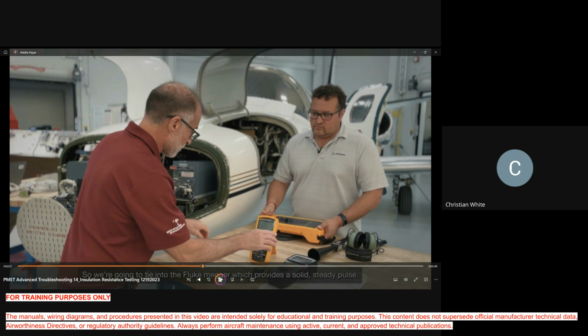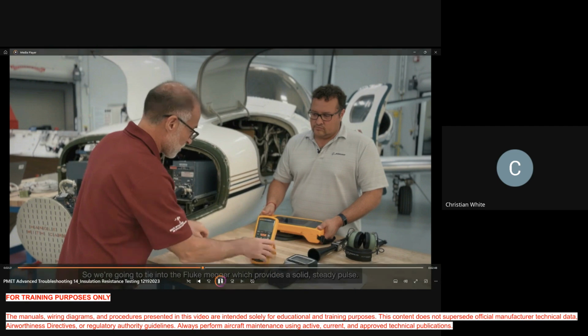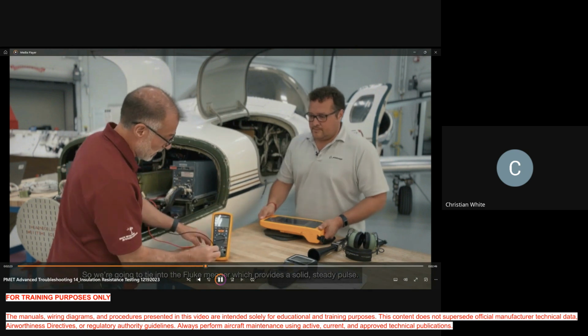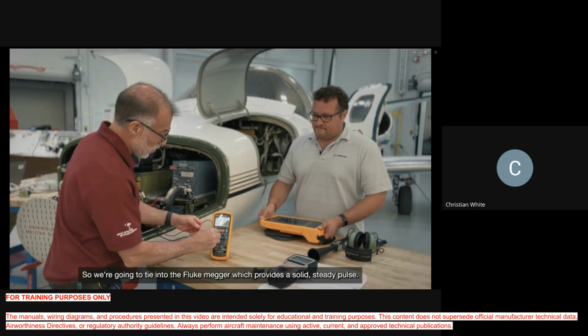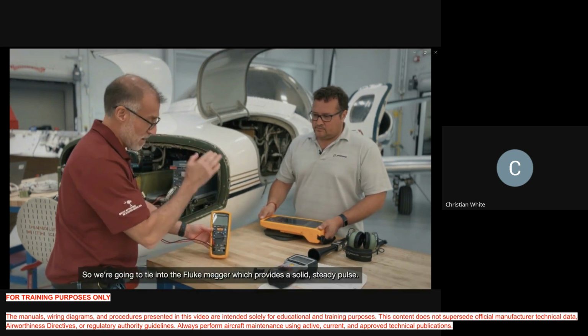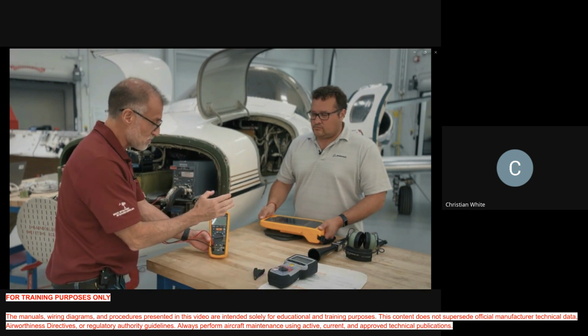Now, if we're going to cheat and use the cool stuff, unfortunately, we haven't talked Mike into buying one of these yet because it's 20 grand. But you're going to see him use this acoustic imager and how we can find electrical faults with this acoustic imager. Okay. So we're going to tie into the Fluke Megger, which provides a solid, steady pulse.